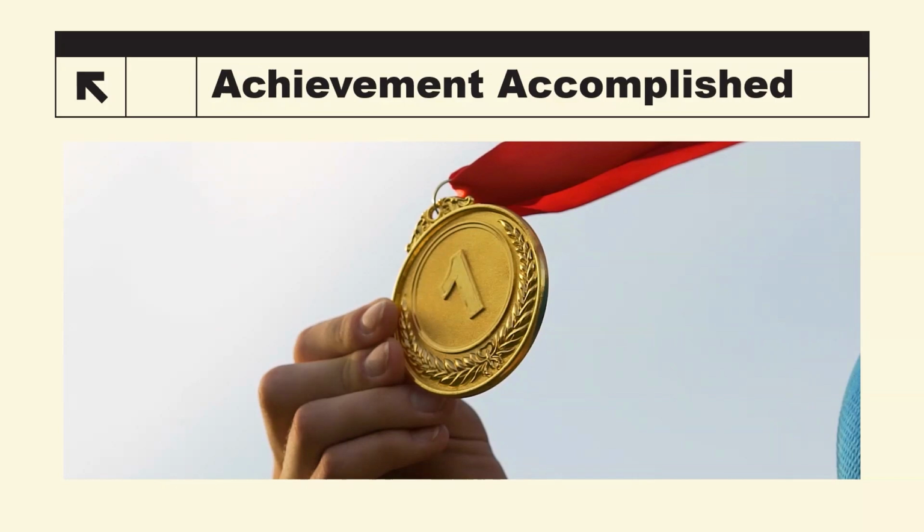There are some speed sheets and whatnot that have been produced that are publicly available in the rating community, so there's not an excuse at this point in time. But at the same time, a lot of people have been saying, yeah, they weighed in the refrigerant, we're good to go. I'm going to type in a number like 5 or something like that in the software, and I've got grade 1, I'm good to go.